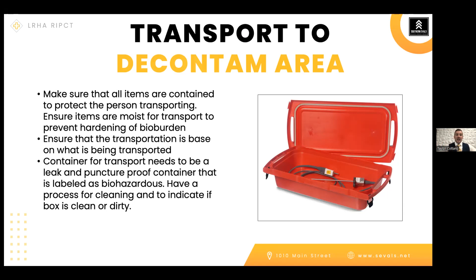Another thing with that box is you want to make sure that you indicate what's in that box. So if it is biohazardous material, make sure that it has a biohazard label on the container. Now, another thing I want to talk to you about is the process. So if we've got a box that's biohazard and we put our instruments in it, we spray it, we transport it to disinfection. Now, what does it look like if we use that same box to transport it back to the area we brought it? Is that still a biohazard box, or do we have a process to clean that box? You want to think through that process and what the visuals are when it comes to that. So again, you need to transport dirty in a dirty container. Make sure that when you transport clean back to where it's going, that the container has been cleaned and it's indicated.